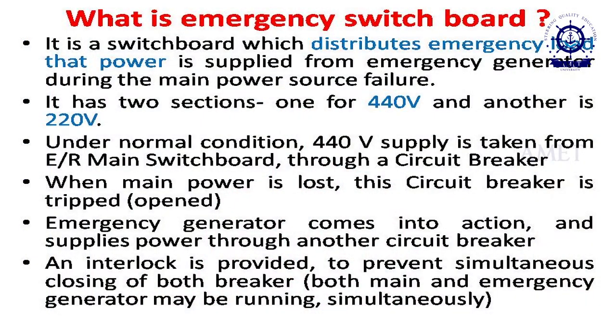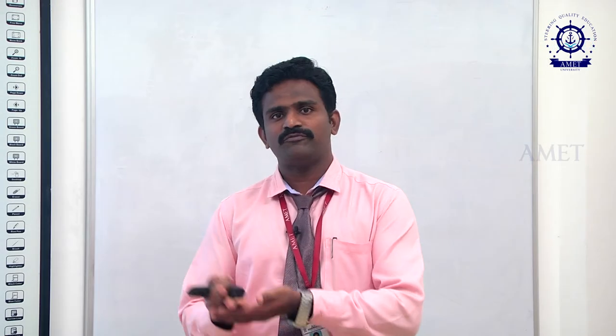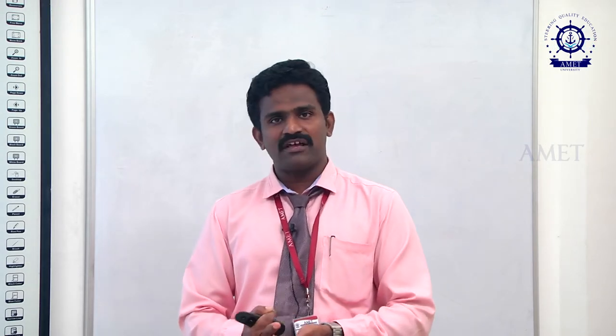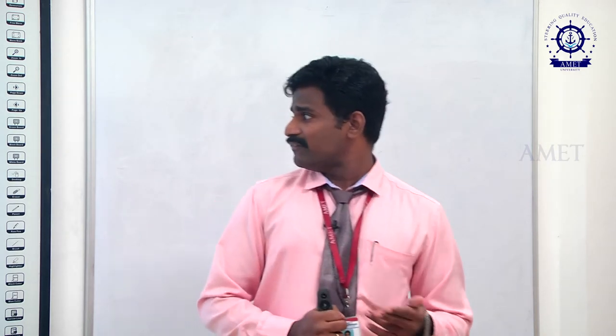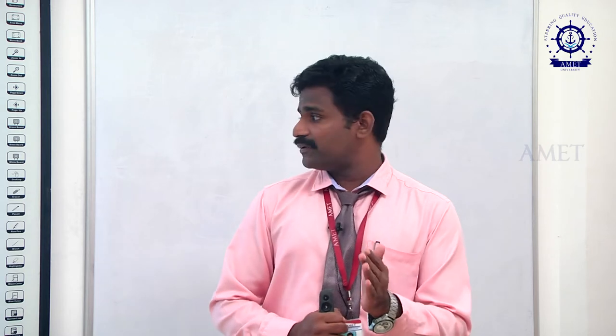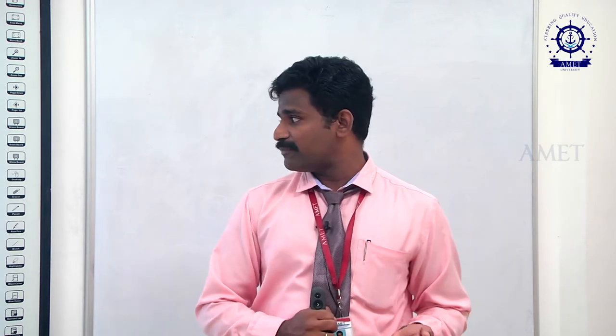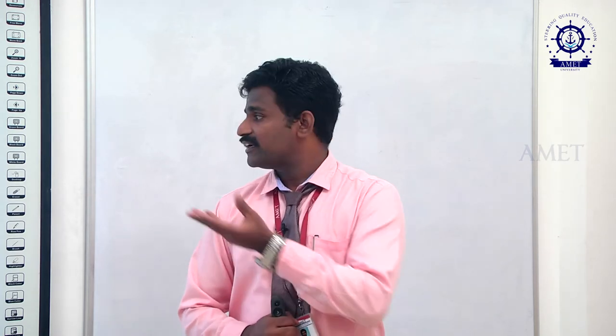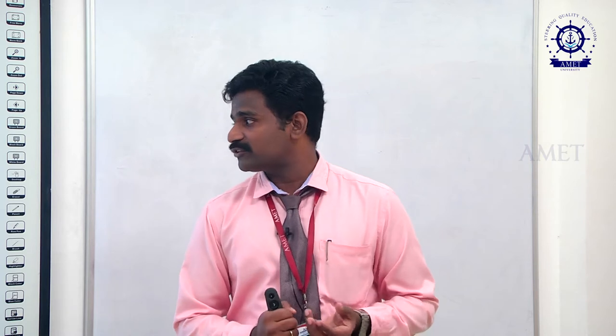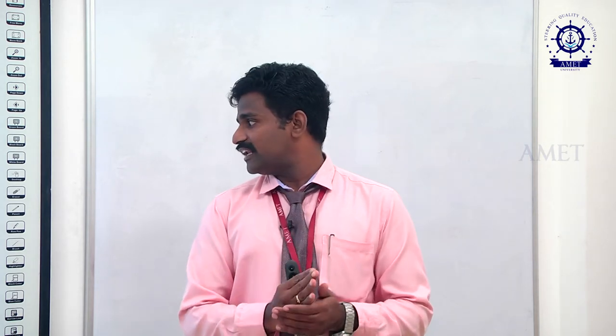They are separated for easy maintenance and backup management. If we only need 220V, we only connect 220V. Connecting both unnecessarily causes fuel loss and power loss. When power is lost, the circuit breaker trips and the emergency generator comes into action, supplying power through another circuit breaker. There is an interlock provided to prevent the simultaneous closing of both breakers.